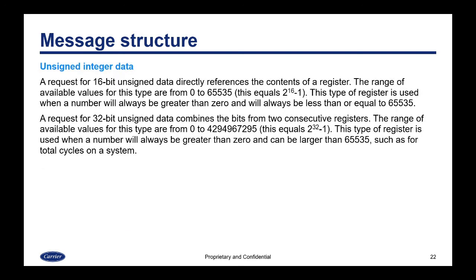A request for 16-bit unsigned data directly references the contents of a register. The range of available values for this type is from 0 to 65,535, which equals 2 to the 16th power minus 1. This type of register is used when a number will always be greater than 0 and will always be less than or equal to 65,535.